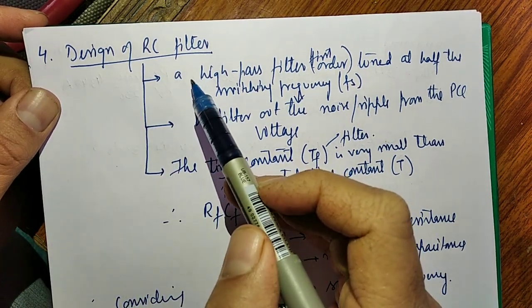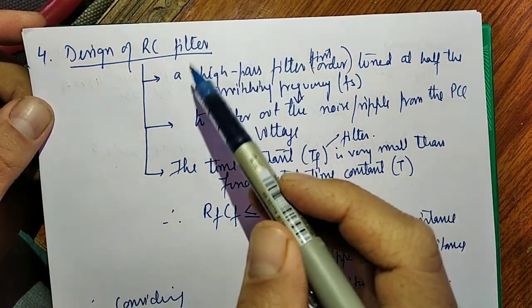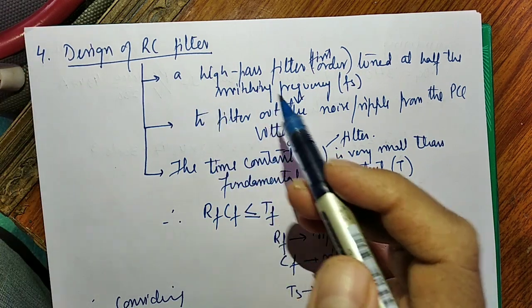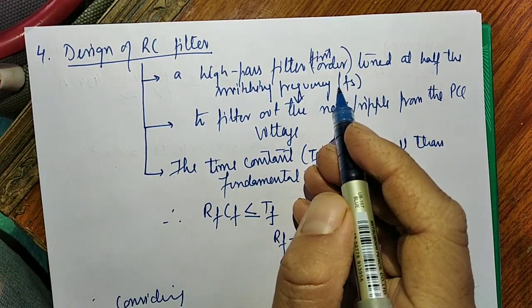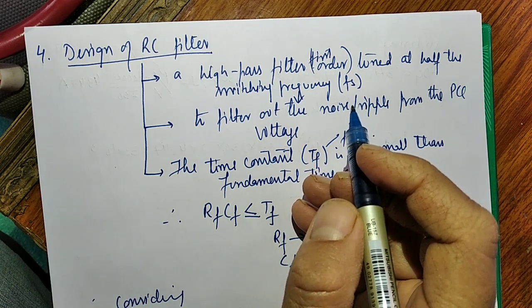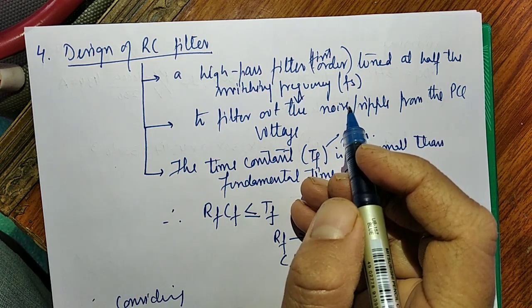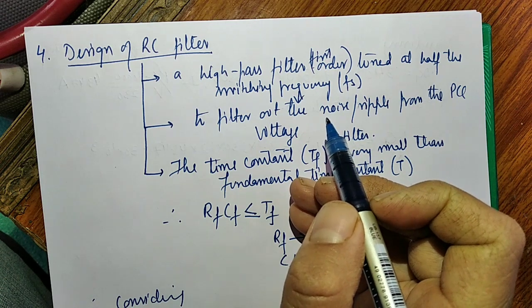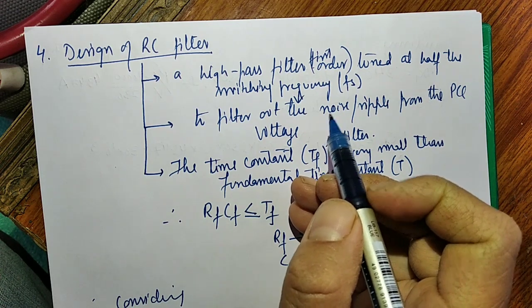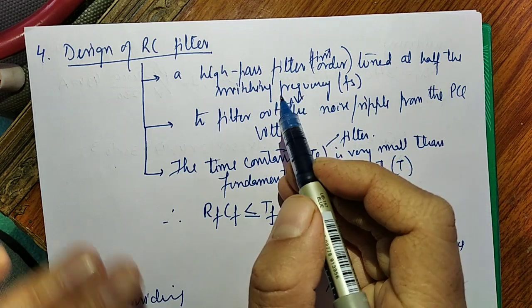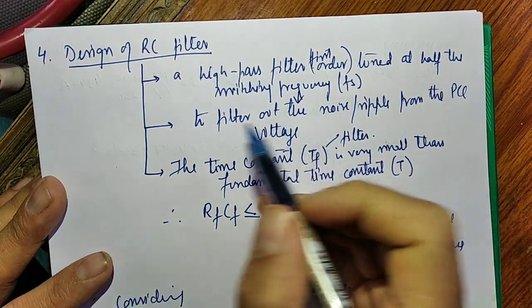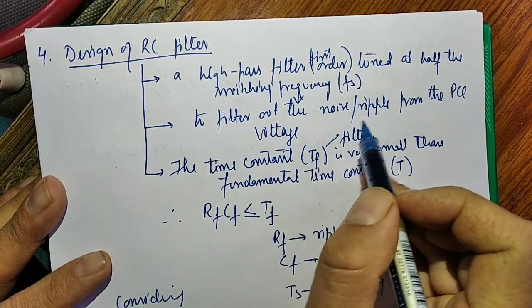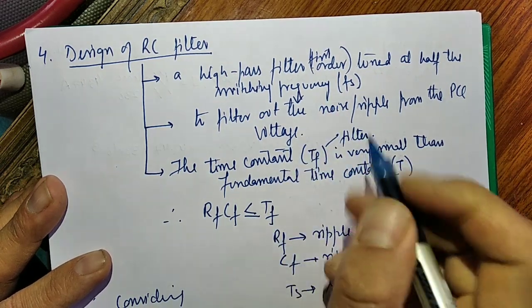Now, the design of the RC filter: this is actually a high-pass, first-order filter tuned at half the switching frequency. For example, if the switching frequency is 10,000 Hz, it is tuned at 5,000 Hz. Its function is to filter out noise or ripple from the PCC voltage.